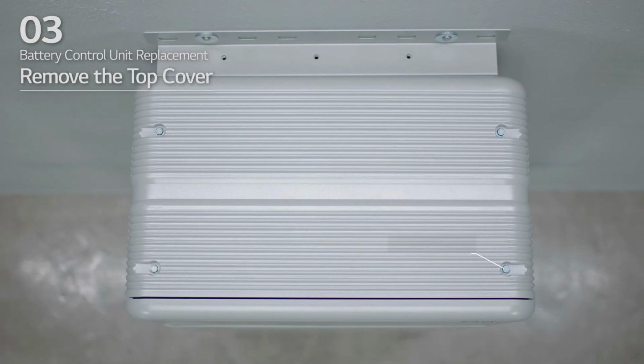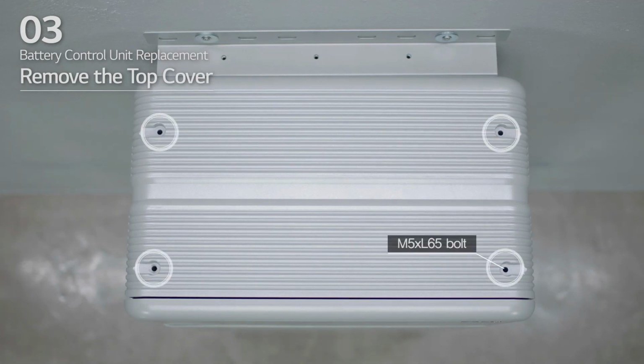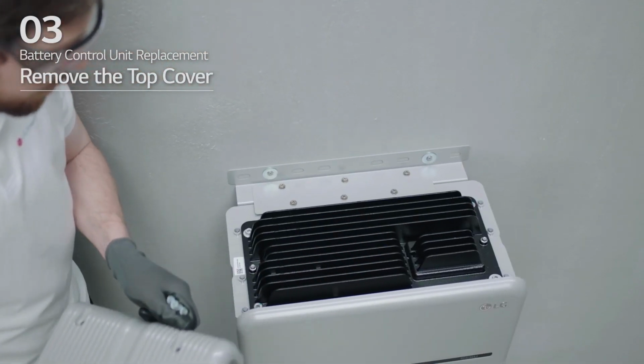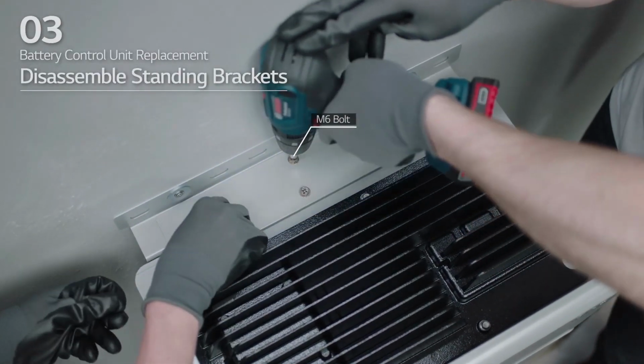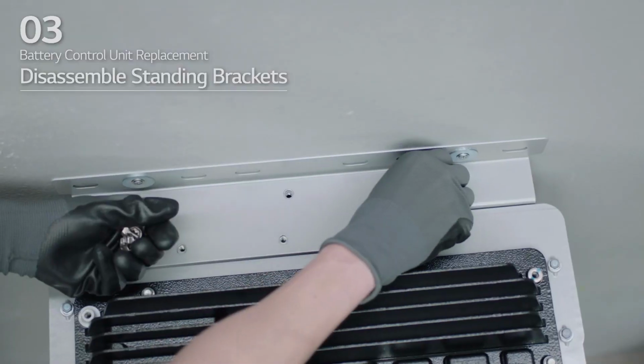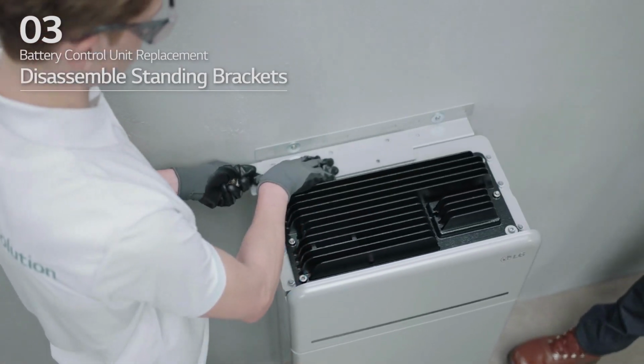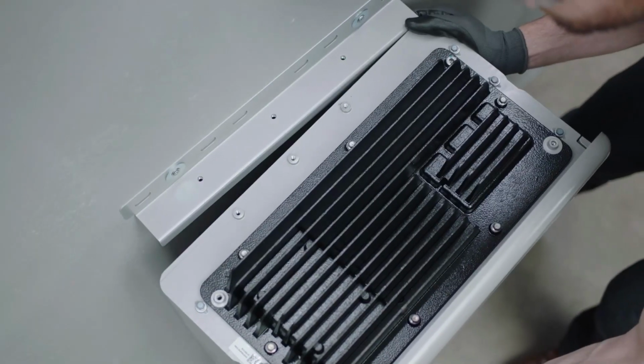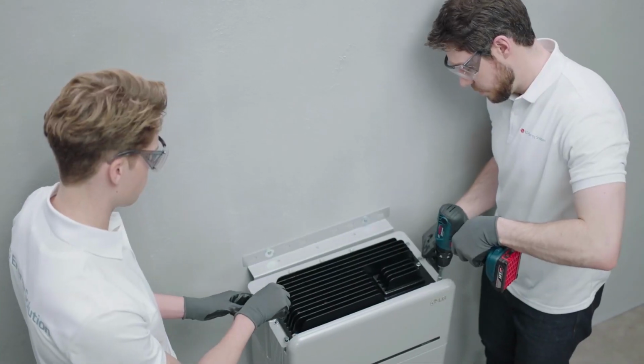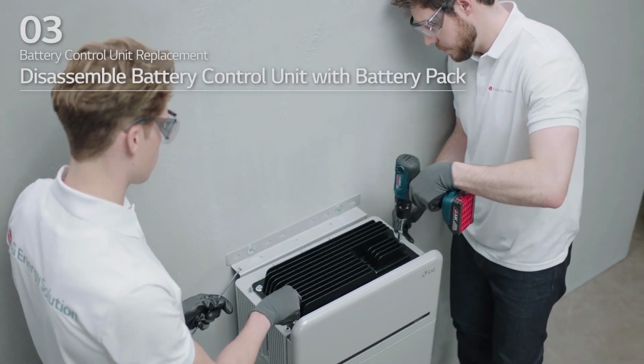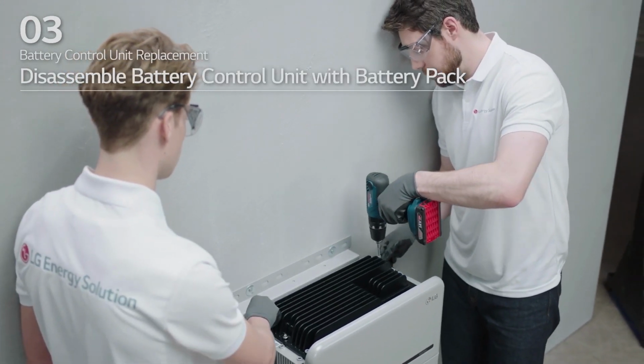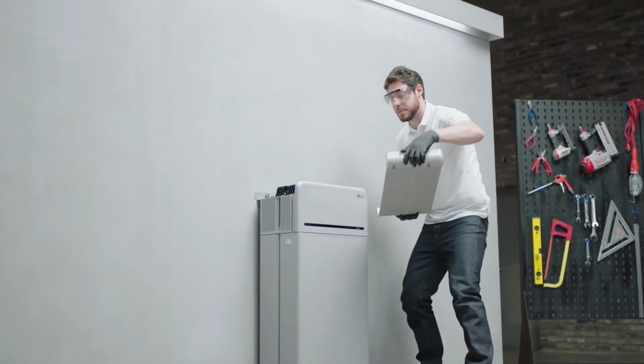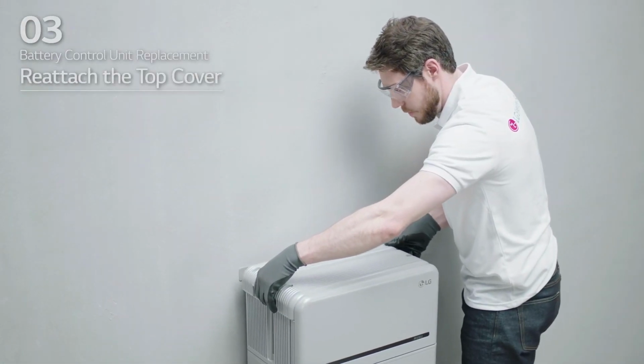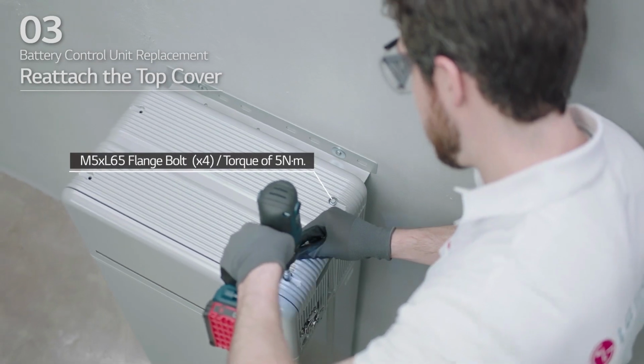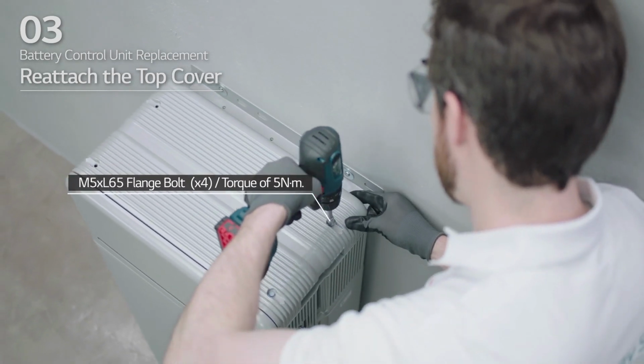Loosen the 4 M5 by L65 bolts and remove the top cover. Next, loosen the 6 M6 bolts and remove standing bracket 2. Loosen the 6 long bolts to remove the battery control unit from the battery pack. Reattach the top cover and tighten it using 4 M5 by L65 flange bolts with a torque of 5 Newton meters.